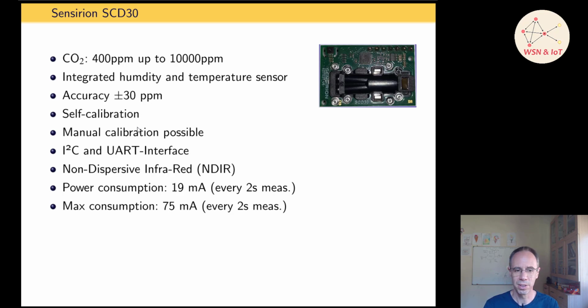When you get the first results, they're sometimes even below 400 ppm, and so on—it calibrates itself after a while. I don't know 100% at the moment, but I think you have to expose it one time to the outside carbon dioxide level, which it takes as a base level, and then it's calibrated with that. When you're using it only inside, and the level is always over 400 ppm, which is what it uses to calibrate, then the algorithm doesn't work as well. You can also manually calibrate it when you know the concentration—you can set it.